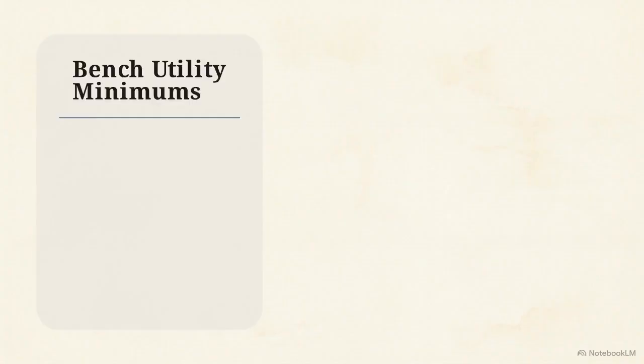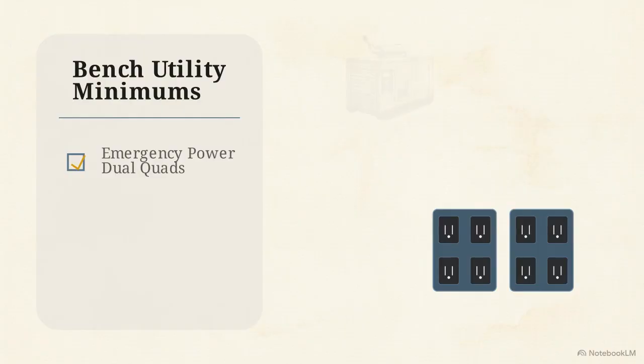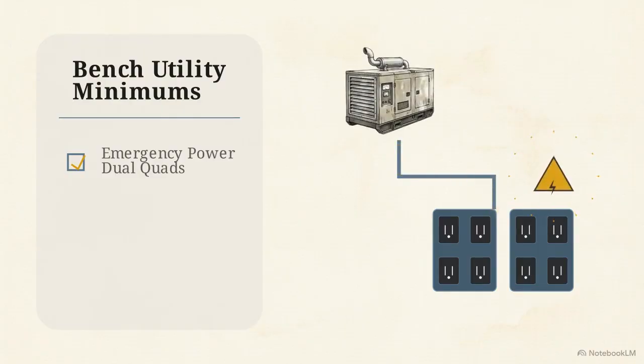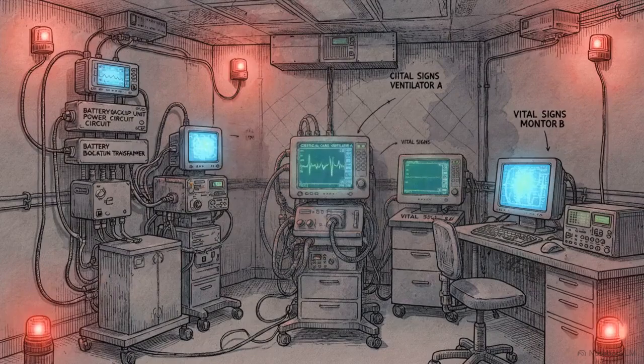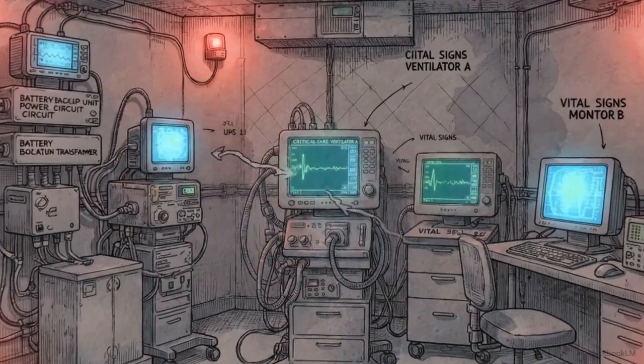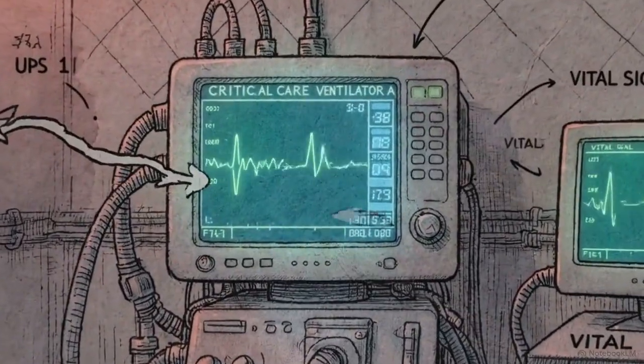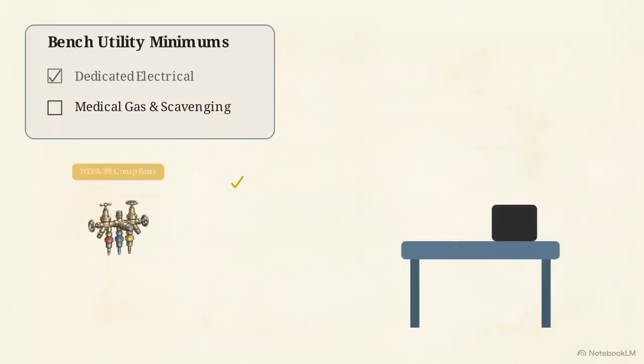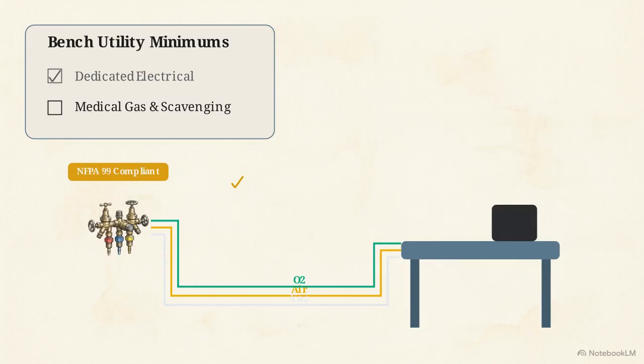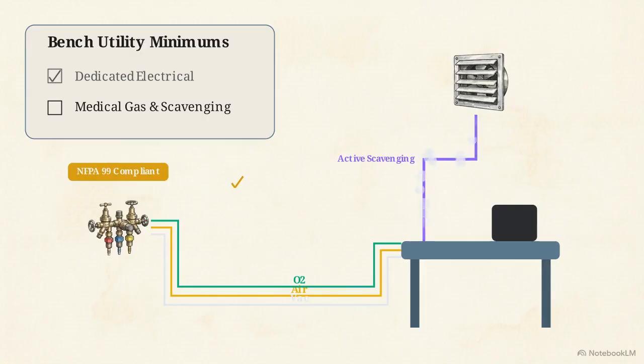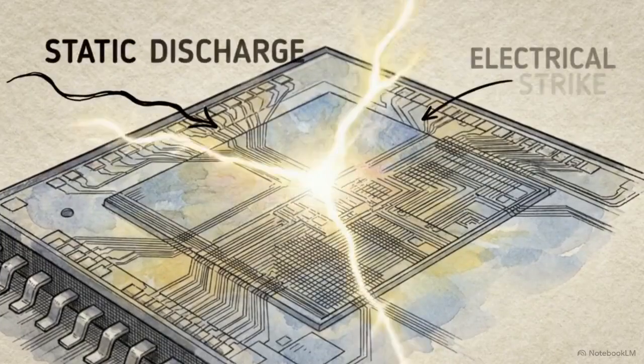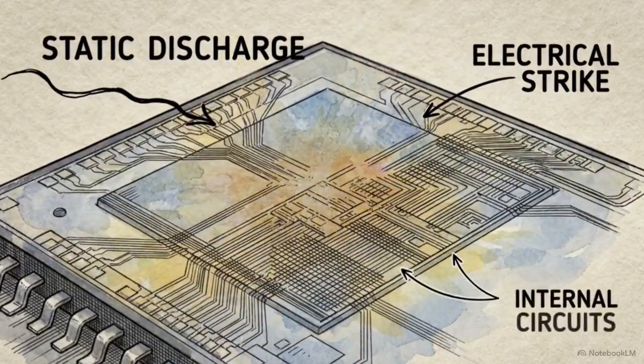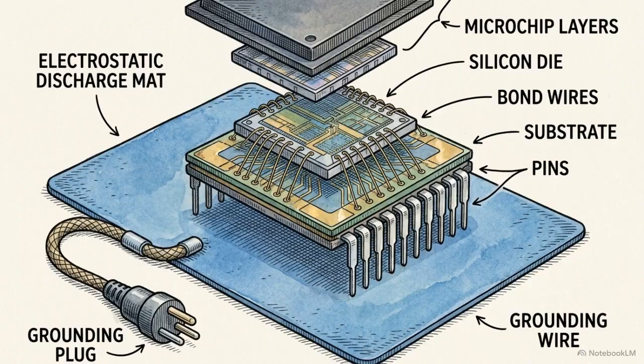This checklist breaks down the invisible utility infrastructure required at each bench, which goes far beyond standard office outlets. The first requirement is dual quad receptacles hardwired directly to the hospital's emergency generator network. While this increases electrical contracting costs, it is the only way to test life support equipment under realistic blackout conditions to ensure battery backups engage properly. For servicing respiratory or anesthesia equipment, you must include piped medical air, oxygen, and vacuum lines at the benches, alongside active scavenging systems to safely remove waste anesthetic gases. Finally, the workspace must be grounded with ESD-safe flooring and bench mats. This infrastructure provides a critical layer of protection for patient monitors, preventing the kind of silent, static-induced damage that can bypass a device's internal safeguards.